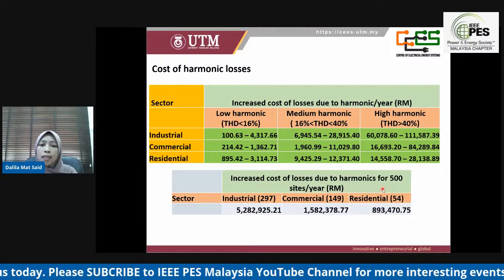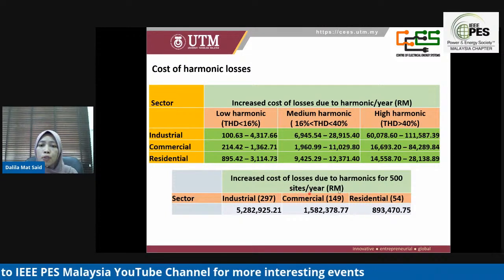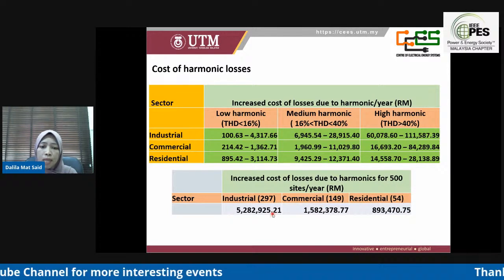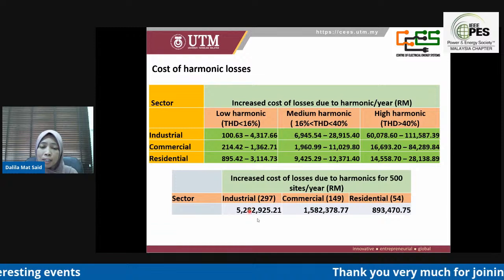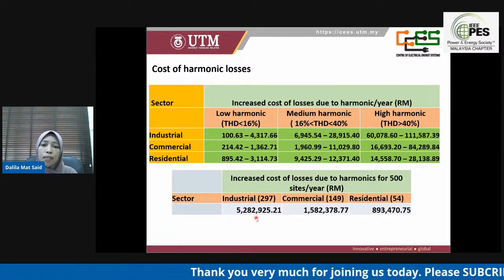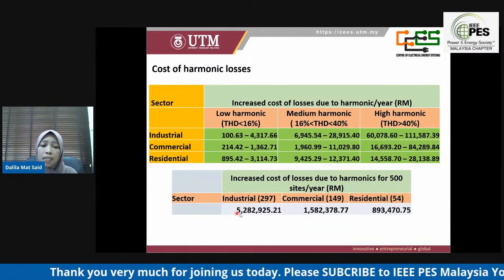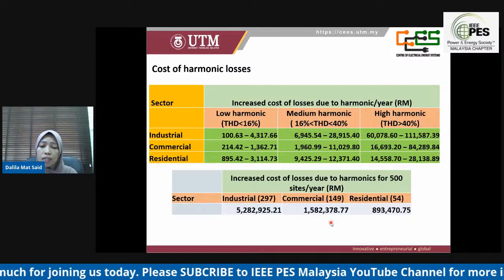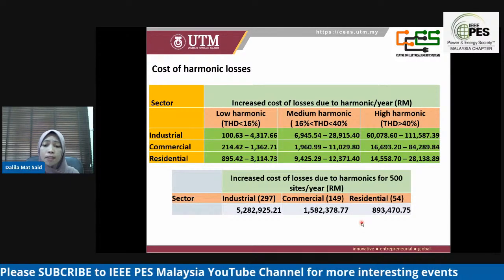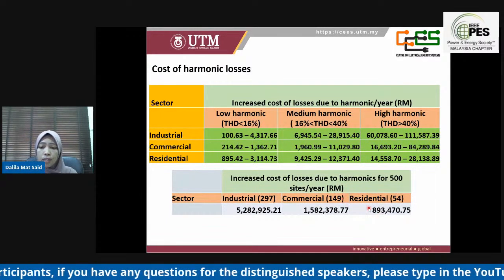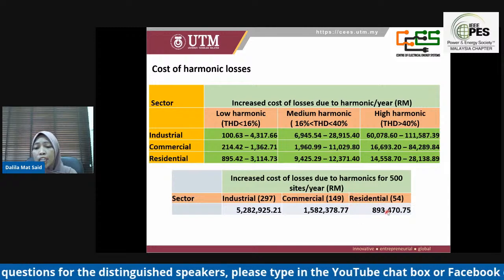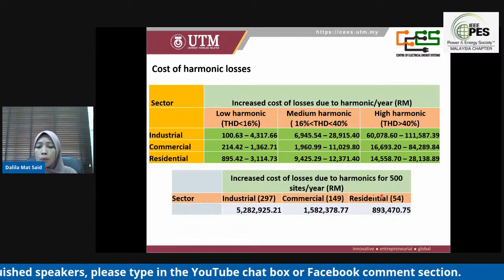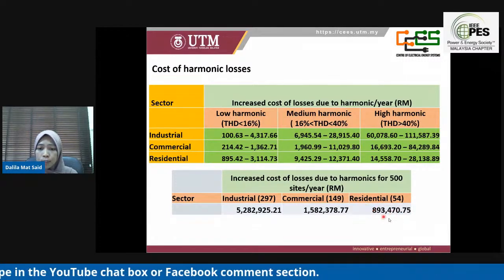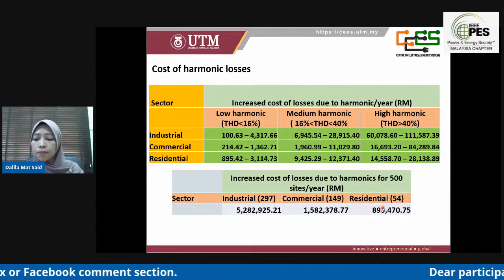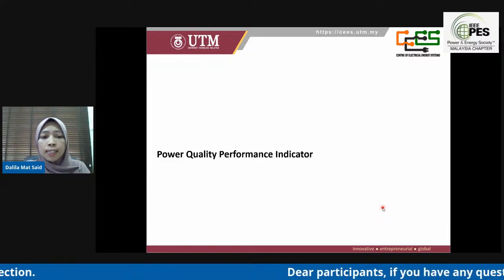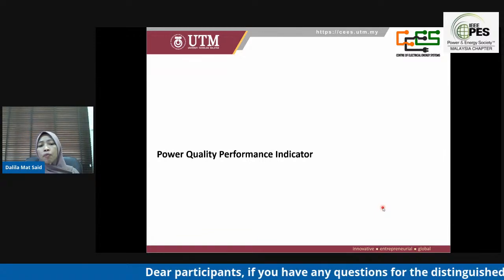Based on the data obtained through the 500-site monitoring, we can estimate the losses of the transformer, and we calculate the increased cost of losses due to harmonics, which contribute about 5 million for industry, 1.6 million for commercial, and around 900,000 for residential areas. Actually, the residential area is not for an individual site; it takes the data from the substation in the residential area. Okay, so the next analysis is power quality performance indicator.